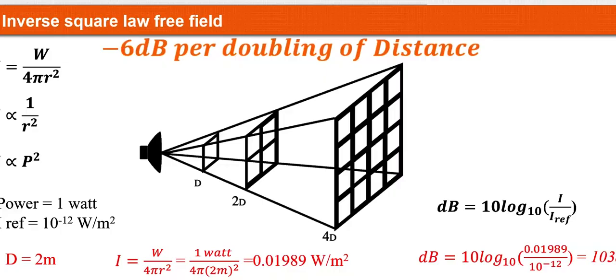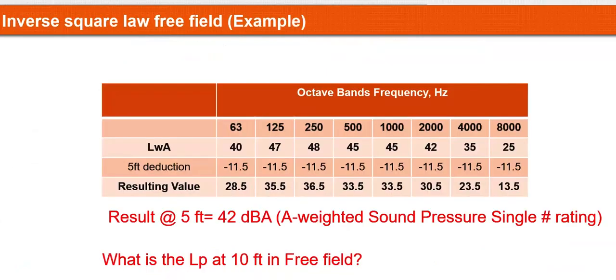All in all, as a quick rule of thumb, use your distance to your advantage. If you are replacing a unit because somebody complained, and you measure 42 decibels at 5 feet, which is pretty low, but in this case it could be louder, don't put the new, quieter unit in the same spot. Maybe put it at least double the distance from where it was before, so that you get an extra 6 decibels of reduction.